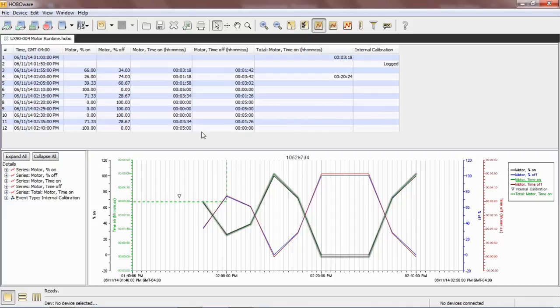You can also export this to Excel and do it there if you wish. Once you have your total runtimes calculated, either by hour or by day or whatever you might need, then you can simply export this file or this column of data to Excel and multiply these times either the energy that you measured previously or the power consumption, and get your actual power consumption based on runtime only and that spot check.